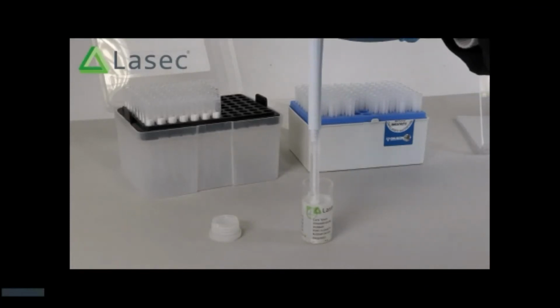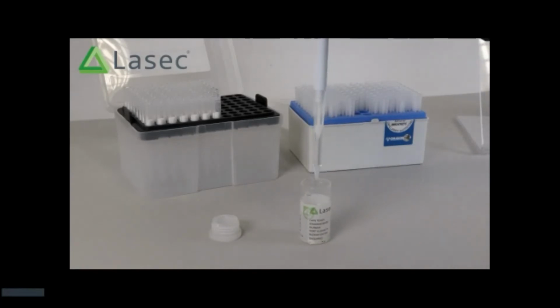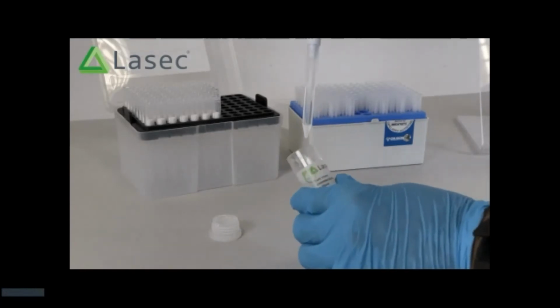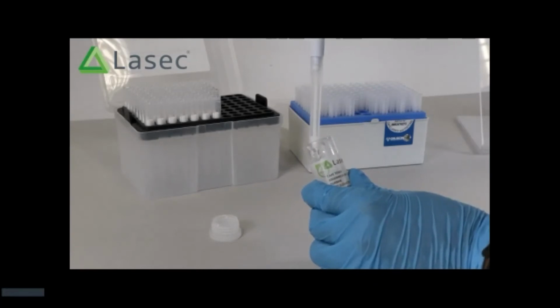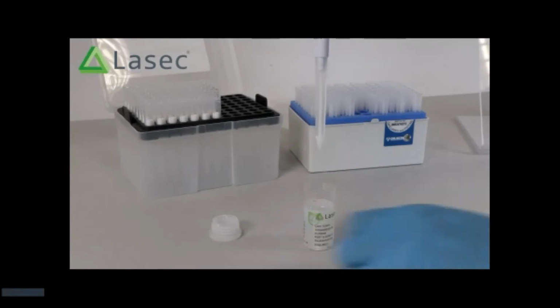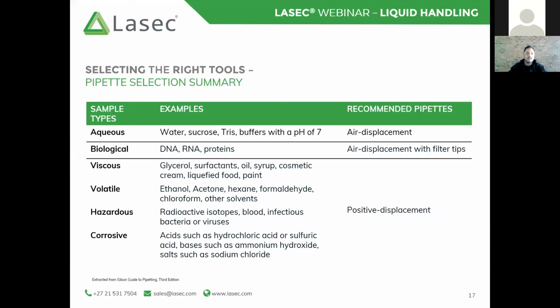Conversely, with a positive displacement pipette, you will see that it's a relatively quick aspiration step. And when I dispense it, it is relatively easy to get most of that solution out. So with very high viscosity solutions, there will always be some left in your tip. But what I'm hoping this video demonstrates is that although there is some solution left in that capillary piston, it is still significantly less than with an air displacement pipette. So you can expect your reproducibility, your precision, and your accuracy to be a lot greater with a positive displacement pipette.